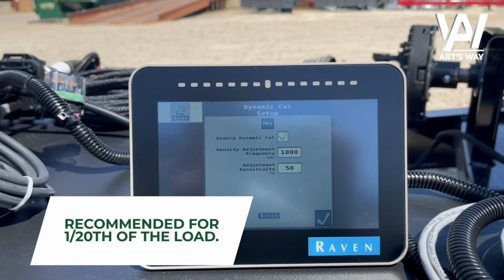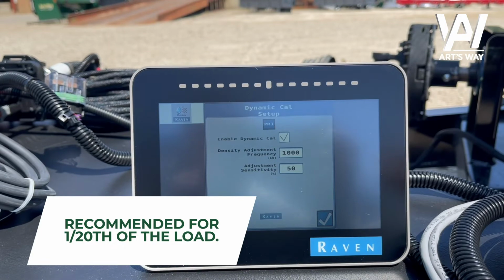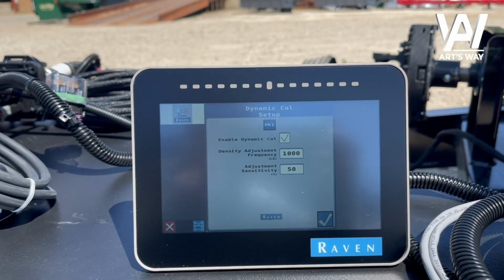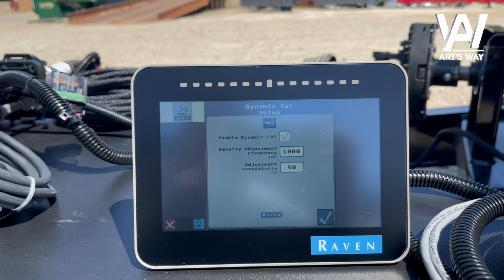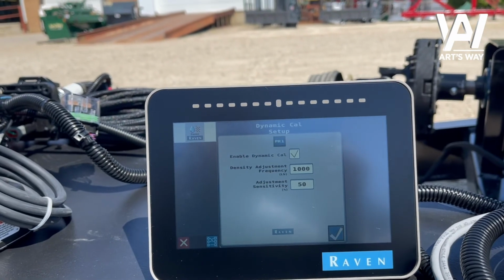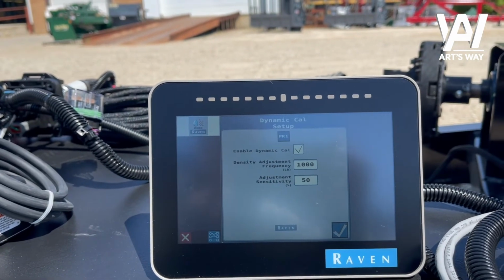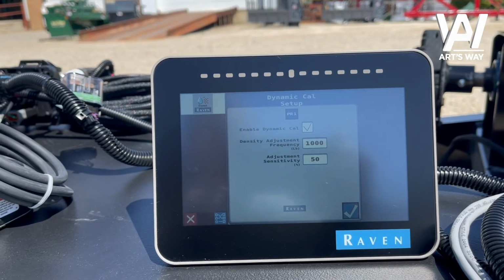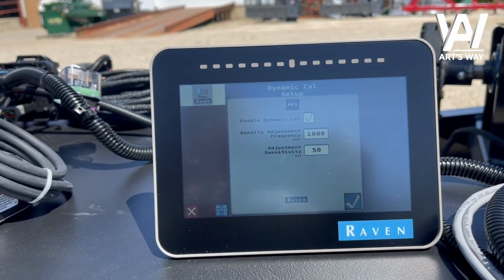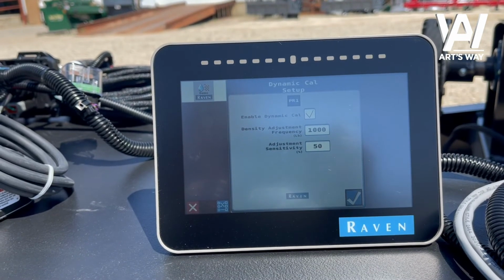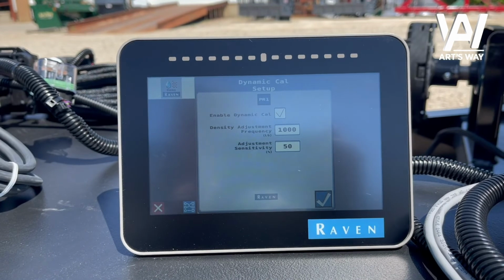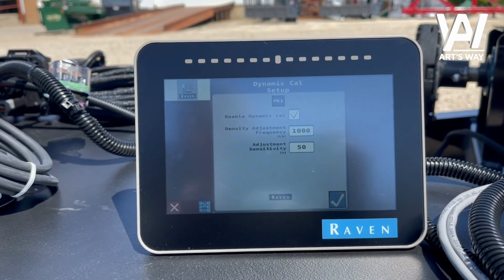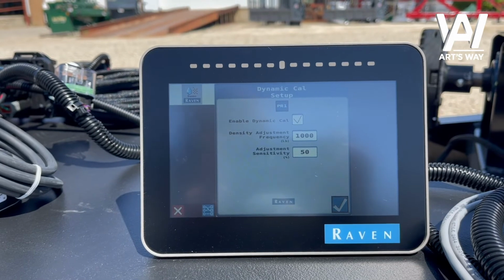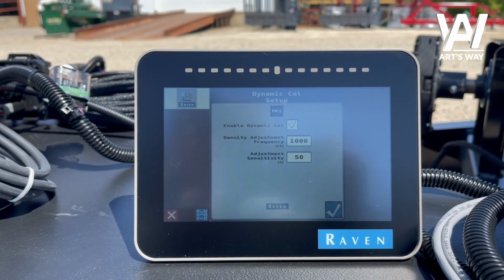From there, we'll go down to our dynamic cal setup. We usually recommend about 1/20th of the load, so that typically equates out to that 2,000, 2,500 range as well. What that does is, at 1,000 pounds as we have it set here right now, every 1,000 pounds that the scale decrements, we'll go back and look at what we said we put on through our rate controller. If there's a discrepancy between the two, the dynamic cal feature will adjust the product density to smooth that out and make sure that we're applying what we say we're applying.